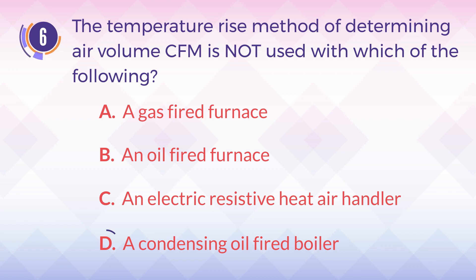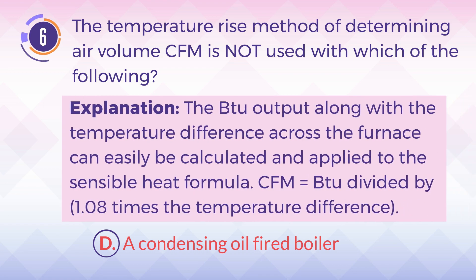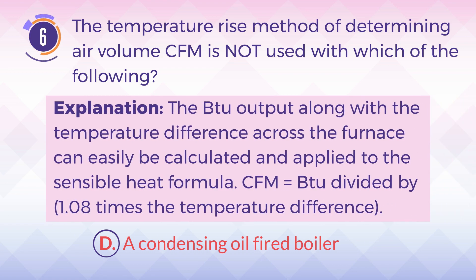The correct answer is D. A condensing oil-fired boiler. Explanation: The BTU output along with the temperature difference across the furnace can easily be calculated and applied to the sensible heat formula: CFM equals BTU divided by 1.08 times the temperature difference.